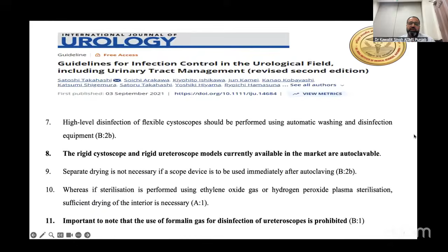And the last slide with which I would like to conclude is the four pillars of high-level disinfection. Number one, pre-cleaning, because the ultimate success of the entire process is determined by the quality of initial pre-cleaning. Second is strict adherence to the contact time. We need to respect the contact time as per the manufacturer's instructions. Third is post-contact dryness, because proper drying and storage prevent biofilm formation. If biofilm forms, it is a failure of high-level disinfection, and lastly, documentation. So I think all of our urologists, all of us, should be actively involved in this sterilization process.